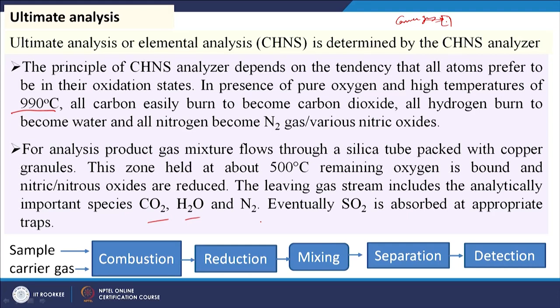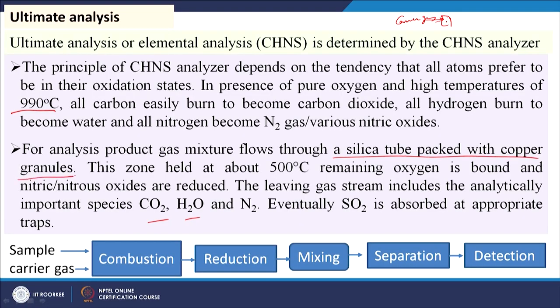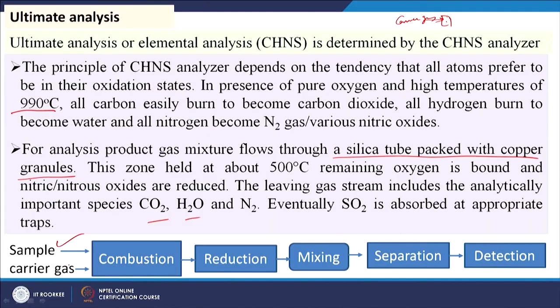We have CO₂, H₂O, N₂, and SO₂. To separate them we need variation in retention time of the different gas molecules in the GC column — that is, their interaction with the stationary phase must be different. NOₓ is reduced to nitrogen prior to entry into the GC column. A silica tube packed with copper granules is used, so the carrier gas along with components passes through it and NOₓ is converted to nitrogen by reduction. Then the mixed gas goes through the separation and detection stage in the GC. The steps are: sample, carrier gas, combustion, reduction for NOₓ, mixing, separation, and detection.